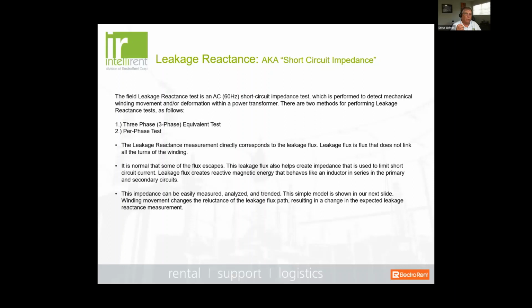But when we do the three-phase equivalent, we'll marry all those results together and then compare that with the nameplate data, the impedance measurement stamped on the nameplate. Well, think of this. Think of a wooden trough, and in that wooden trough is water flowing down the trough. Normally, as the water flows through, it's going to have some normal resistance. It's an old wooden trough, and you may have some leakage that spills over or whatever, and this is normal.